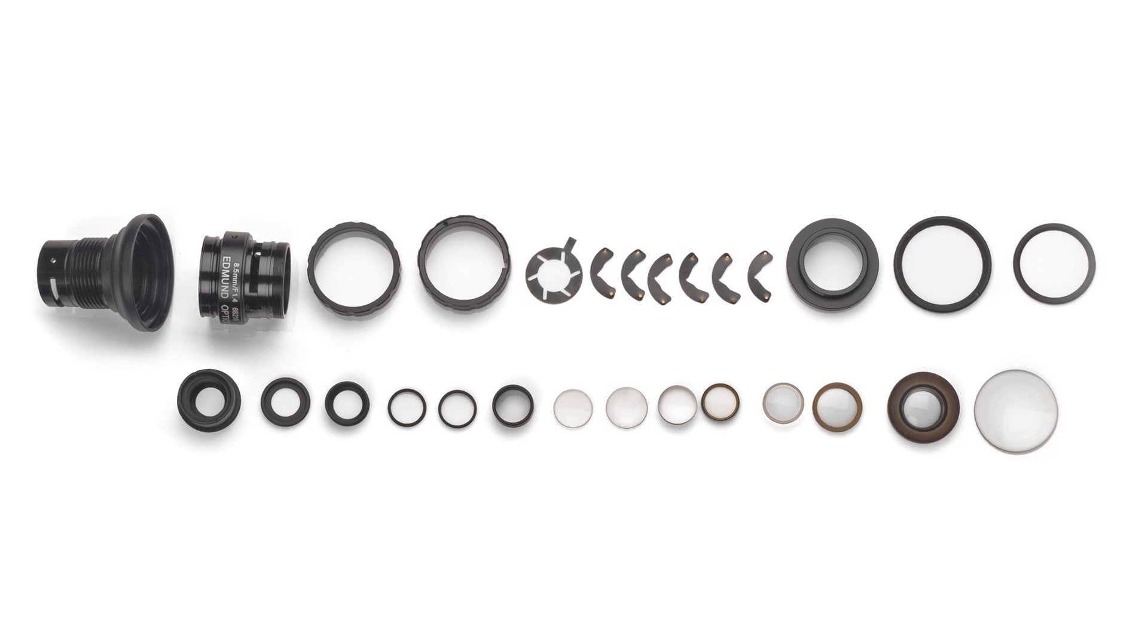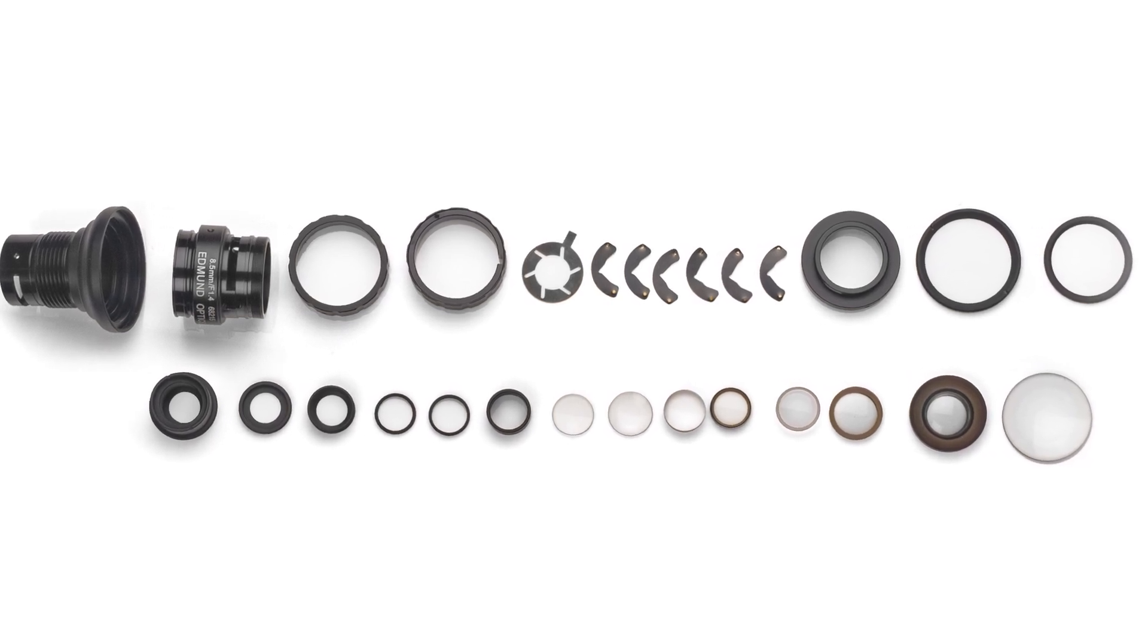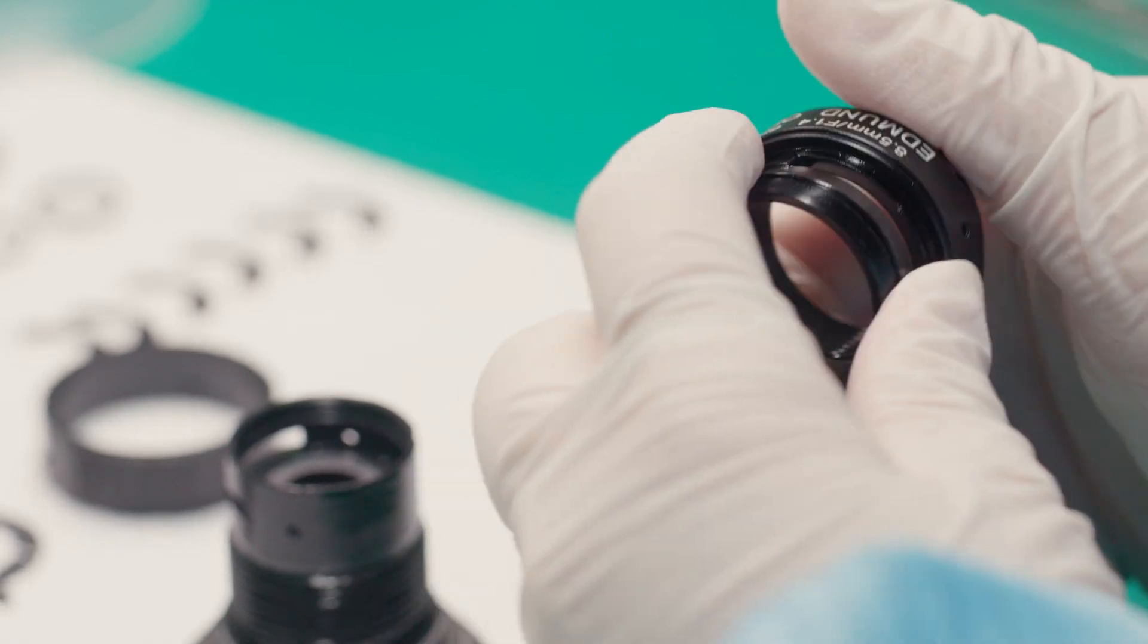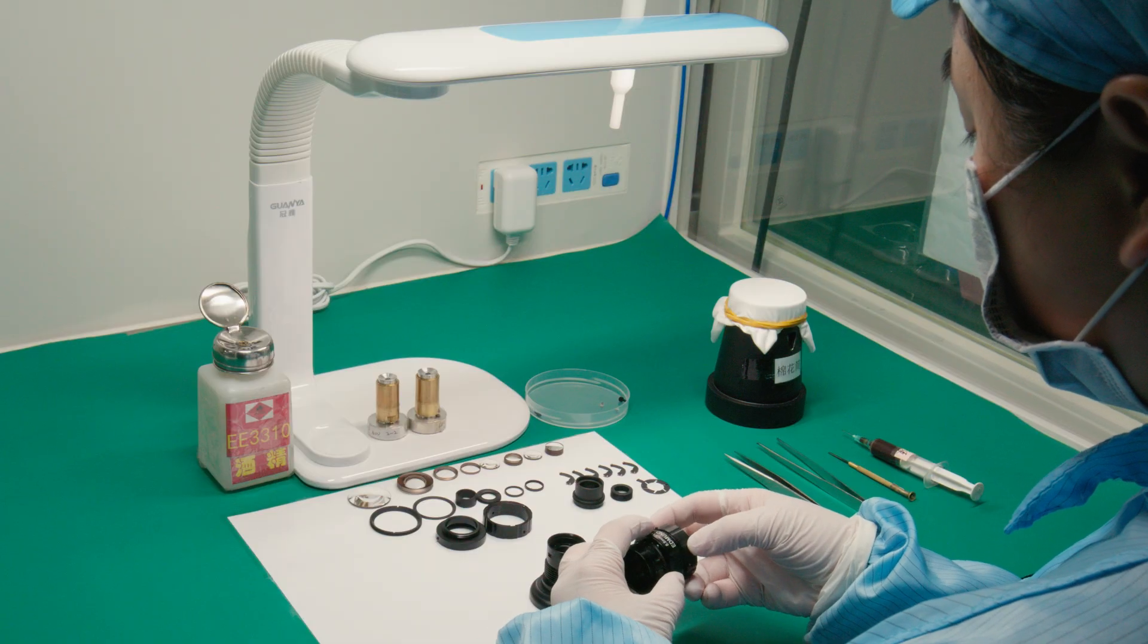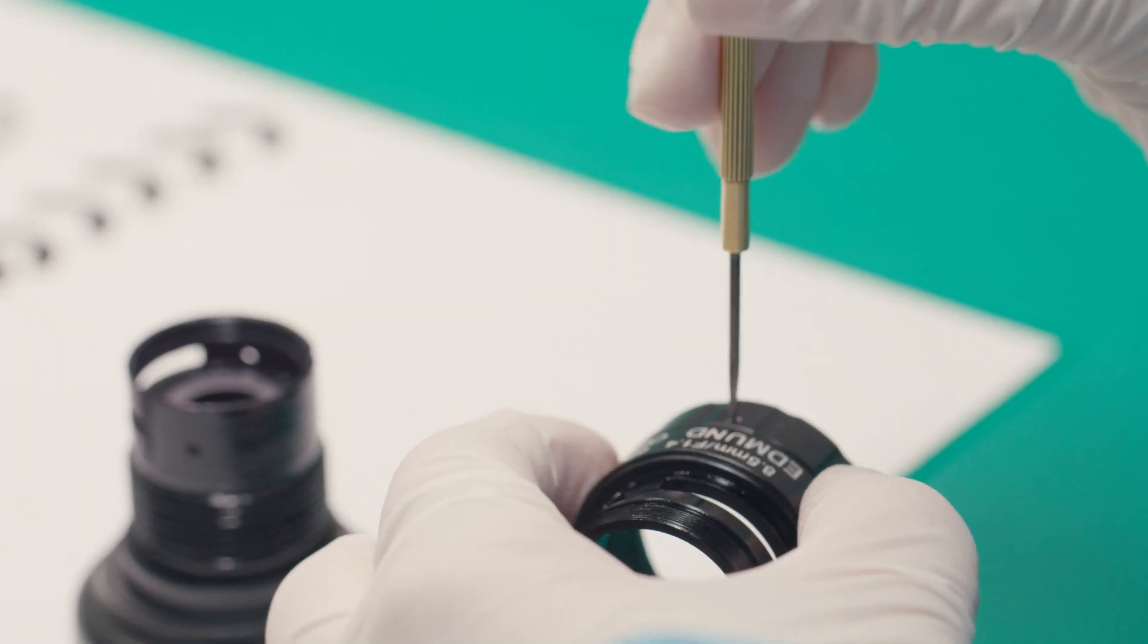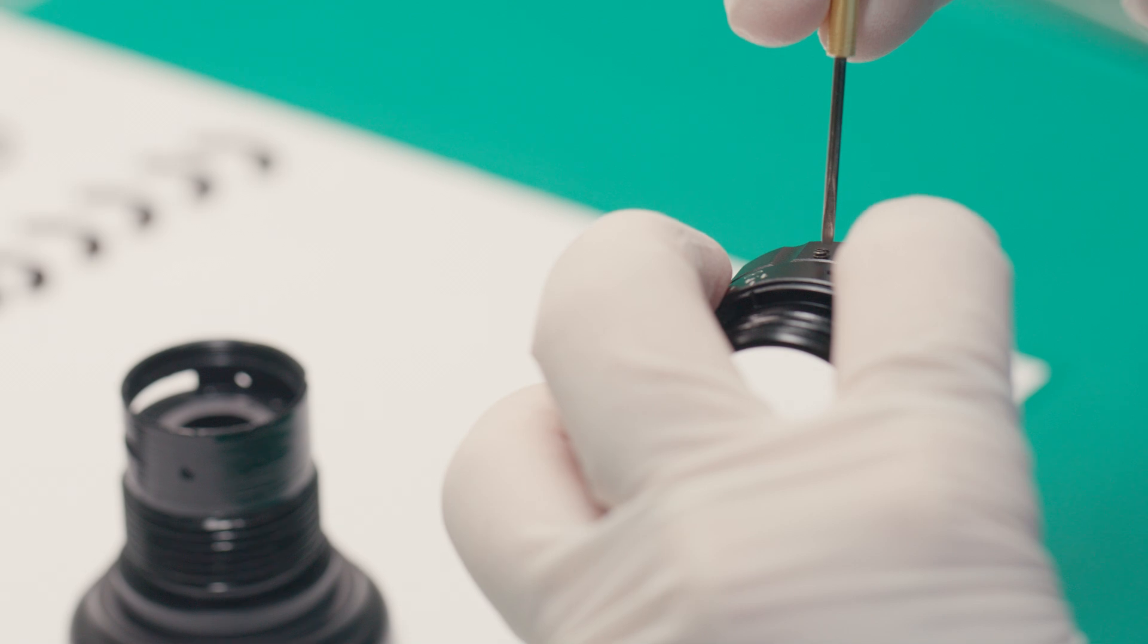Now, all components are ready to be assembled by a skilled technician. The multiple components of the helical focus mechanism are assembled together. Set screws and adhesives are used to affix the focus and iris barrels in place.